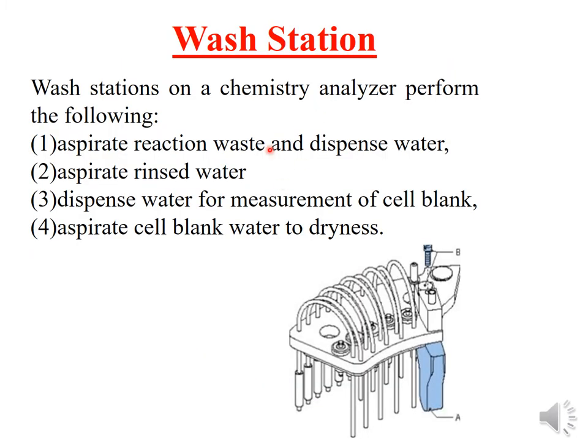The wash station aspirates reaction wastes and dispenses water to wash the cuvettes. It aspirates and dispenses the rinsing water, then dispenses water for measuring cell blank, and also aspirates all the blank to dry the cuvette.